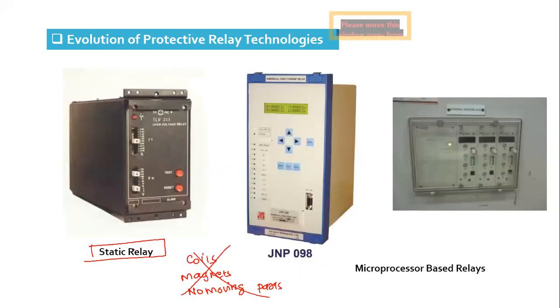So static relays are the relays. Now what is the problem with static relays? Static relays are very sensitive to disturbances and impulses, because they operate on low voltage applications. So sometimes if there is a transient, the components of this relay may easily get damaged. So that is an issue with static relays, they have reliability issues in comparison to electromechanical relays. I am not even discussing microcontroller based relays yet. So generally nowadays static relays are not used; they are obsolete, and rarely will you find applications of static relays.